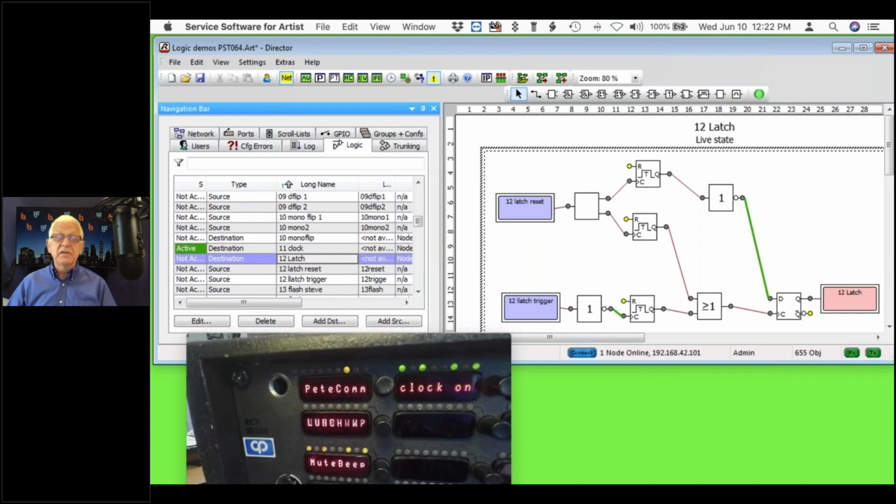Now, if I turn on this latch, trigger it, it just happens. Boop, it's done. It's going to turn on that latch, and that trigger could be that I've lost power somewhere, or that a UPS has gone down, or something like that. And I would want to know that when I came back in the morning. So this latch is going to stay on until I reset it.